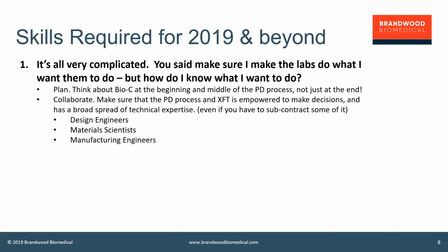You would need to involve your manufacturing engineers, because the manufacturing engineers will be able to tell you, well, when we converted this material into this component, this is everything else that we did to it at the same time. So we used a mold release agent, we used a lubricant when we cut the steel, we plated it, we coated it, we anodized it, everything that they did in the process. So that needs to be factored in because it's all part of the final product that we're evaluating.